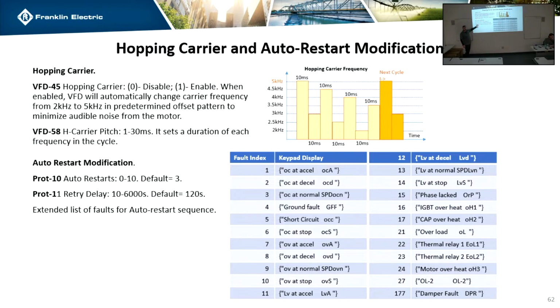So if you have another BMS system that's looking for whether this drive is tripped, and you have this set to 10 and 6,000, it's going to be a very long time before the drive actually signals the system that something's wrong. It's just going to be sitting there doing all of its restarts. So 3 at 120 is kind of a happy balance where it will retry and you're going to get a signal to your system fairly quickly.